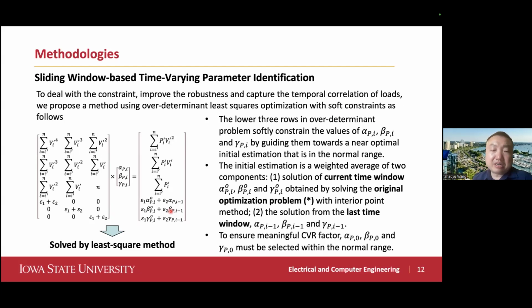I'll skip all the details, but you can get a feeling after solving this matrix. You can find alpha, beta, gamma for each time window. Remember, each time window has at least three measurement points, meaning active power and voltage at the feeder head, at the substation level.